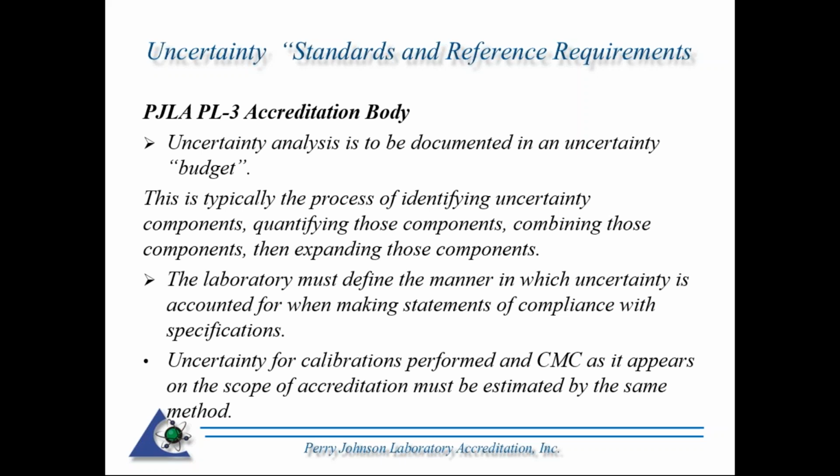And we do specify in PL3 that if you do not address it in your own uncertainty procedure, then we would require you to do it as stated in PL3, where we have a couple examples of phrases that can be used on the calibration report, or you can simply use the terms pass indeterminate, fail indeterminate. Uncertainty for calibration performed in CMC as appears on the scope of accreditation must be estimated by the same methods.